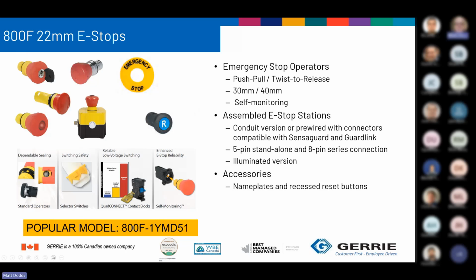And so, what does almost every machine need? An e-stop in some shape or description. The 800F is a 22mm mounting push button with a variety of options. However, unless it needs to be mounted to the panel, the 800F 1YMD51 is an illuminated e-stop button and comes in a standalone enclosure with a 5-pin connector, and the wiring is compatible with SensaGuard and GuardLink systems. So again, it offers quick and easy installation and indication of a trip condition.